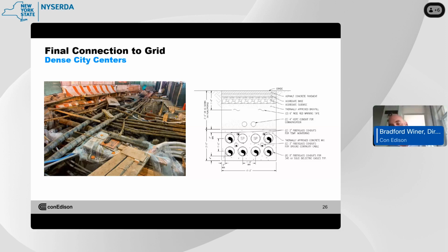Now, I'd be remiss to say every street in New York looks like this, because it does not. But when you're installing XLPE or a solid dielectric system within the general right-of-ways, the roads people are traveling on, it's really important to consider how much space one needs. If you look at the drawing on the right, it shows an example of what an electric circuit installation looks like—you've got conduits wrapped in concrete for protection.